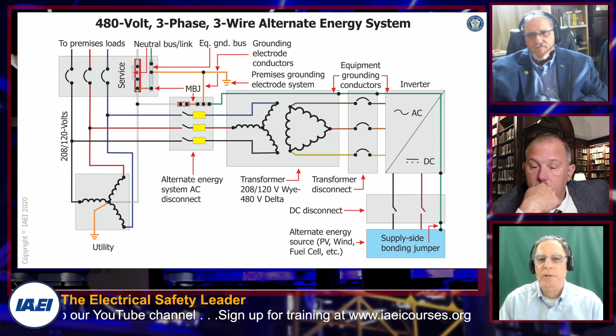But if you go 2 more slides, this is where the real headache comes. Wow, why transformer? Why? Because, yes. And this is because I said so. This came out of several inspectors on the East Coast, and then it hit California in Pete Jackson's area. A lot of solar systems, our alternate energy systems, now have a Y at 480 volts, then they're going to a Y at 208/120. And when you look at the grounding and bonding here, you have to be extremely careful that you don't reground the neutral downstream of the service. That's a boo-boo, particularly if you have ground fault protection.